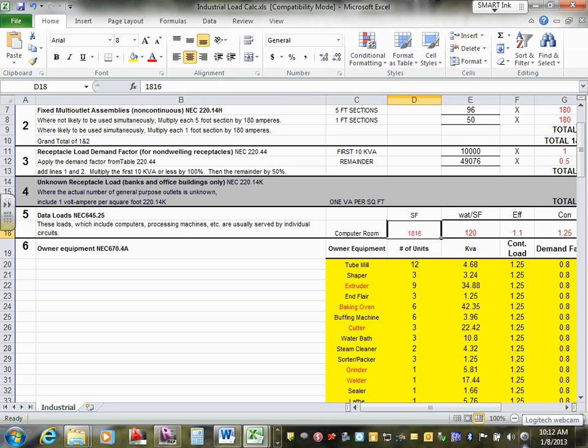Now this load, but before I go there, here's the square foot of the data center that we have. Everybody can see the square feet of the data center right here. Multiplied by 100, actually it should be 150. You remember how we changed it yesterday to 150? Okay, so that's multiplied. Where is the 150 coming from? The design criteria for the data center is 150.